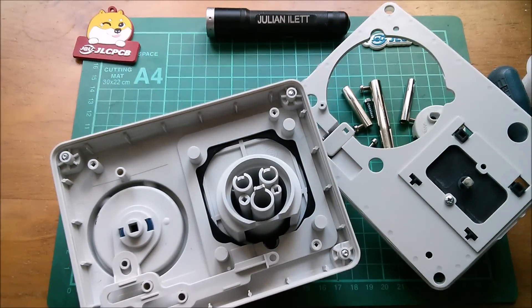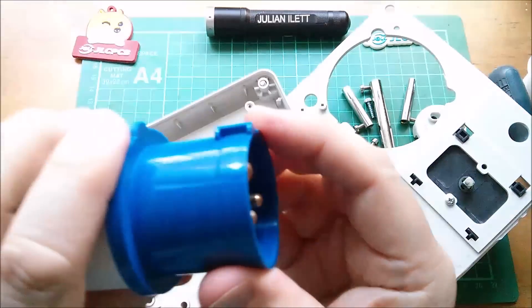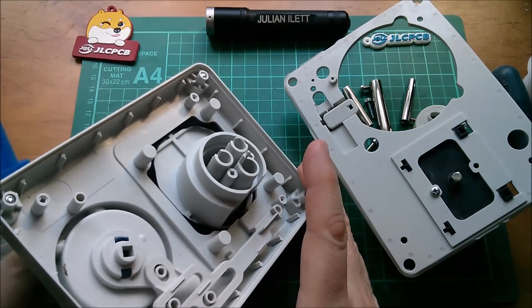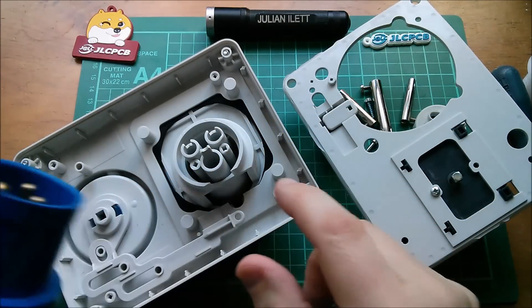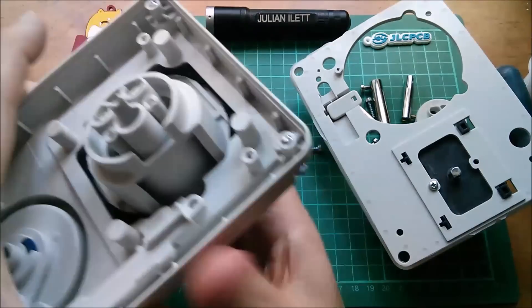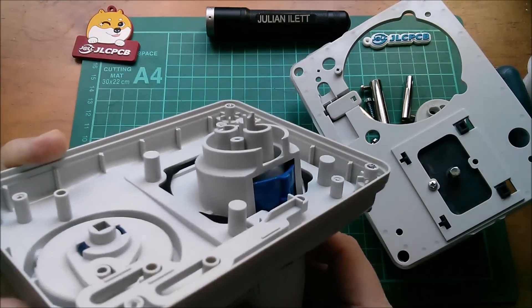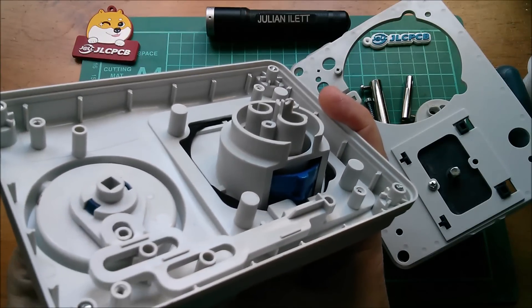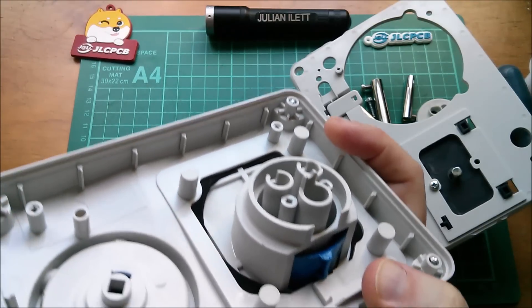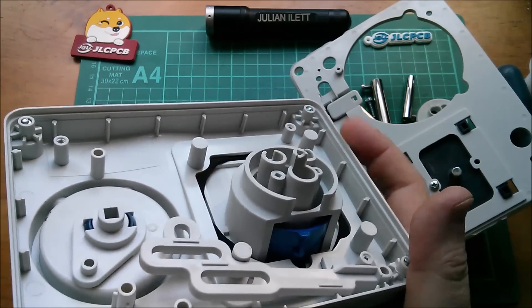That's what locks the plug in. Here's a 16-amp CEEform or commando plug. You can see the little keyway piece is a certain length long — the slide is designed to sit behind this key piece so that the plug can't be withdrawn. That blade locks itself underneath the blue plastic key that runs down the keyway, and that prevents you from withdrawing the plug.